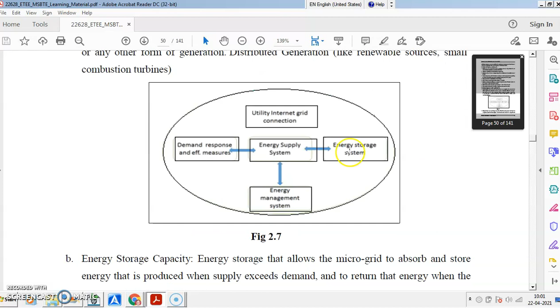Then the demand response system and efficiency measures. A more sophisticated microgrid will incorporate the ability to control end users in a smaller manner, which allows generation and storage responses to be optimized. For example, non-crucial loads like lighting and water heaters can be automatically shut off or turned down to maintain the energy flow to crucial loads. So demand response is especially associated with measurement, limit and control systems.